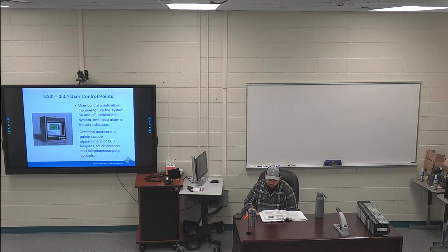3.2.3, telephone or computer control. The last note on page 25 is also highlighted. The NFPA does not permit remote resetting of a fire alarm system that has signaled an alarm. So this would be from somewhere else, from another location. You can't silence an alarm unless you are physically there and see that there is no alarm. They do not allow remote resetting of fire alarm systems, and everybody can see how that can be pretty dangerous. Not allowed.